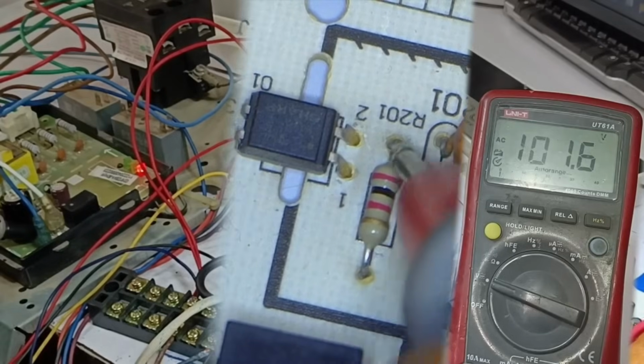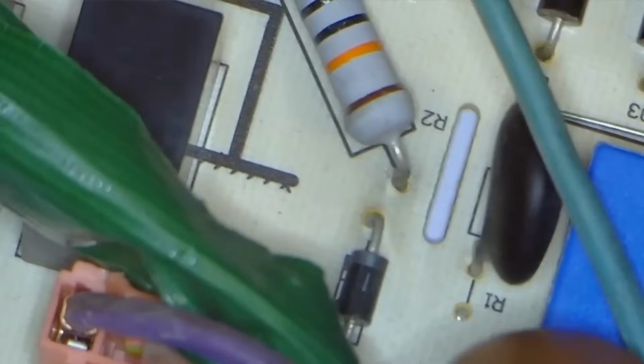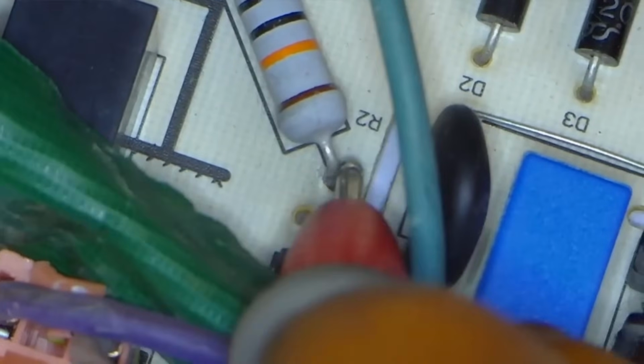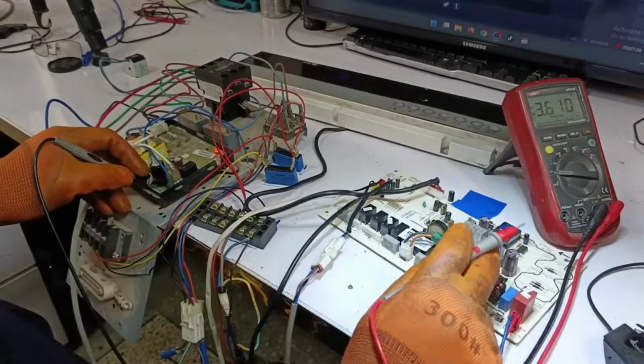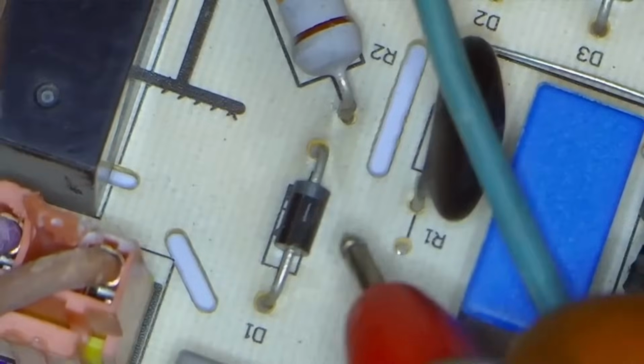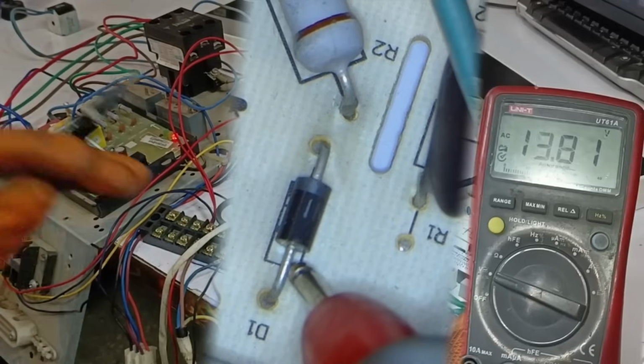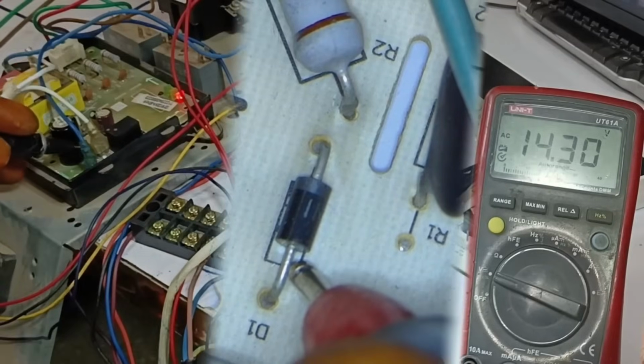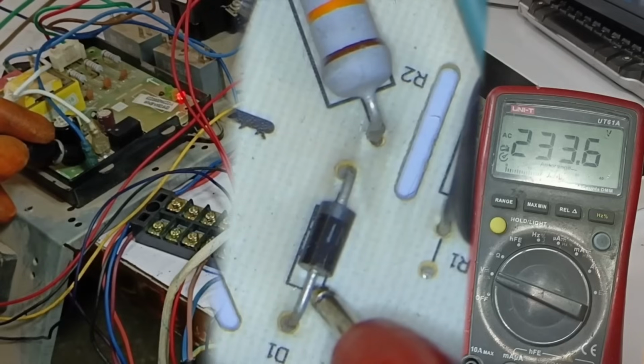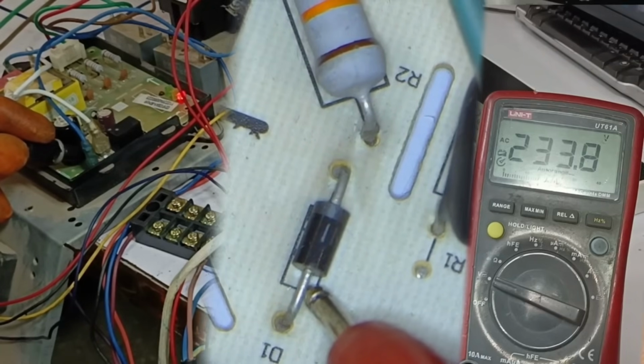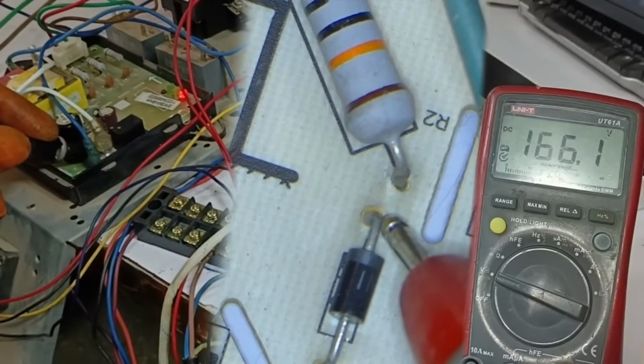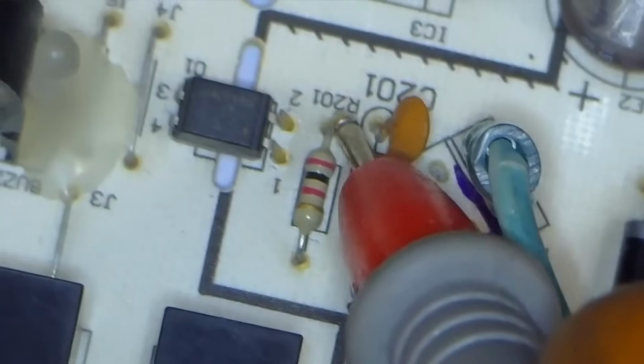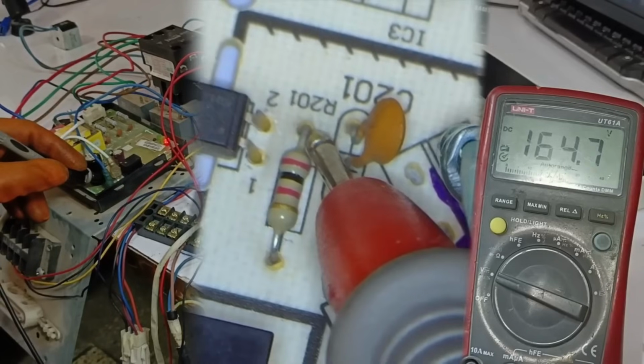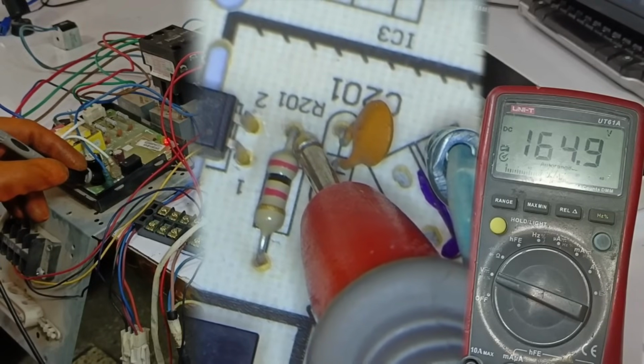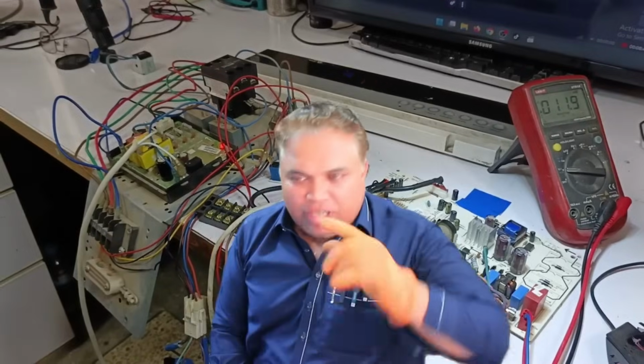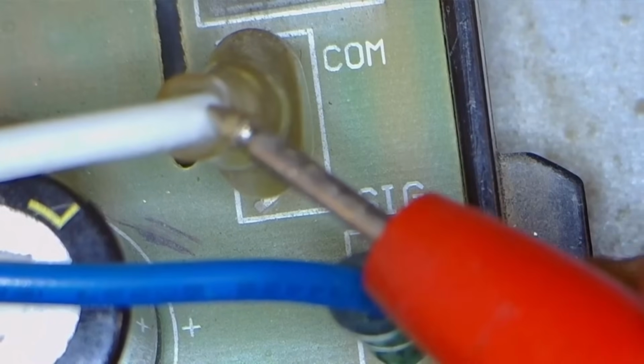Now if we check further ahead, we are still getting 90 volts. Now let's check the voltages at R2. Here as well, we are getting 93 volts. When we follow the circuit step by step, we come to a diode D1. Let's check the anode side of D1, while keeping the neutral at the outdoor unit's common point. As you can see, we are getting 233 volts here, which means this part is working fine. Now, checking the other side of the diode, we get 166 volts. Similarly, when we check at R201, we are getting 164 volts there as well. This means that when we check from the common point, the signal is properly present and everything is working fine.